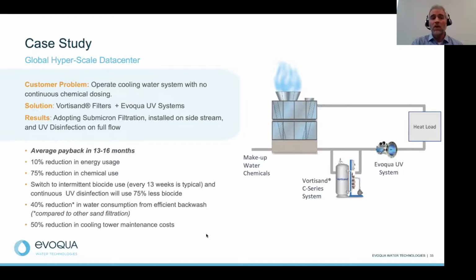non-chemical treatment program for them. So with Vortisand, we're able to reduce their suspended solids down below 1 micron, allowing them to achieve about 10% savings in energy. And then they were able to see significant savings in chemicals through the utilization of the Evoqua UV system. And then Vortisand was able to deliver a 40% reduction in water consumption because of our shallow bed, and then an overall reduction in cooling tower maintenance costs of about 50%.